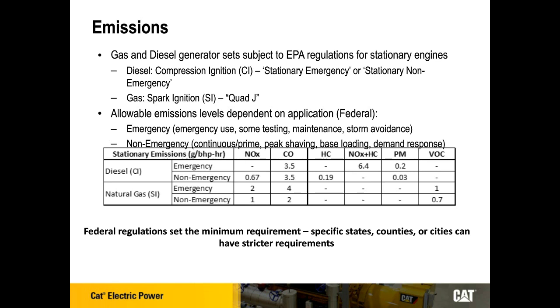On the emission side, both natural gas and diesel generator sets are subject to EPA regulations here in North America for stationary engines. On the diesel side, speaking of compression ignition, we have two different types: stationary emergency and stationary non-emergency product, both on the diesel side. When you speak specifically to the gas product, the spark ignition product, you speak under the EPA regulations for the Quad J regulation. So similar regulations, but different for both the diesel and the natural gas product.